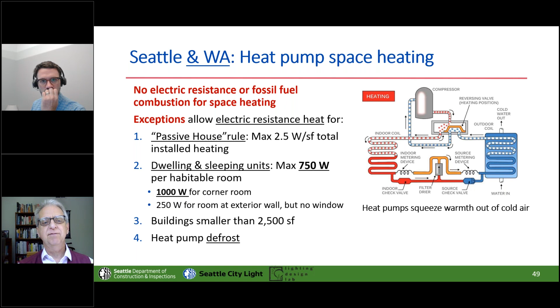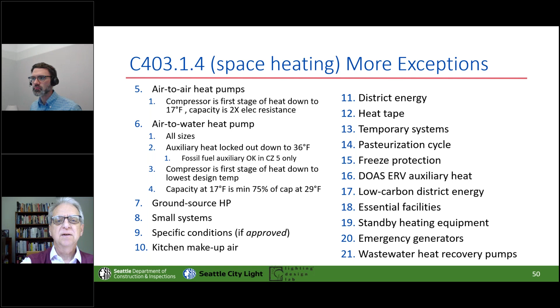But otherwise, we got a whole bunch more that relate mostly to either very small loads or very occasional loads. If you have to do a pasteurization cycle, that's very not often, or for loads that just come up when it's very cold outdoors, you can have some additional electric resistance. But notice that none of those for Seattle permit gas.